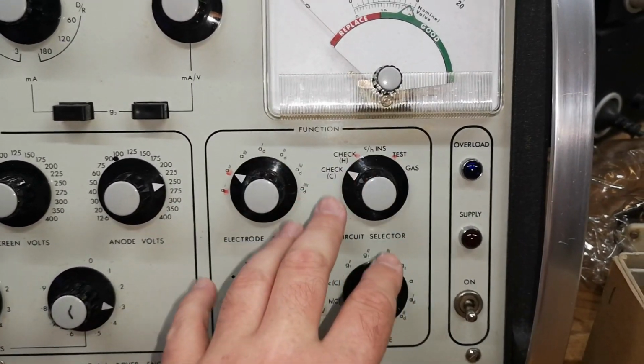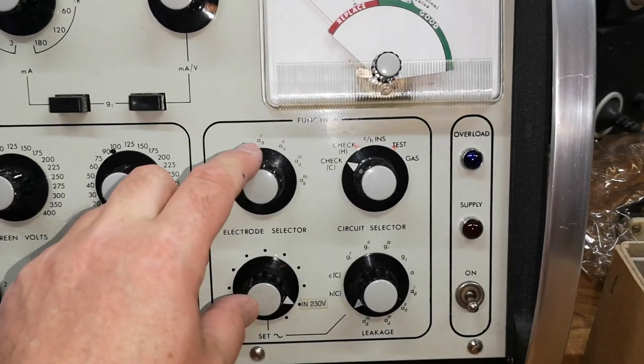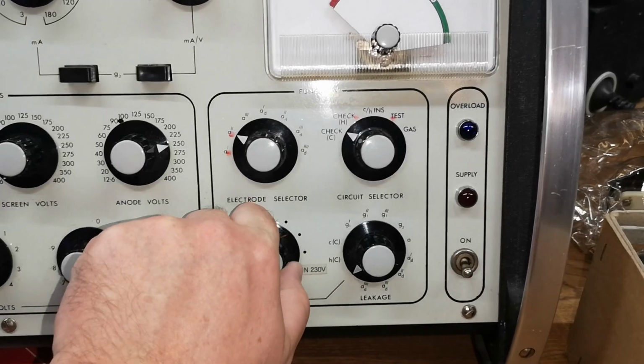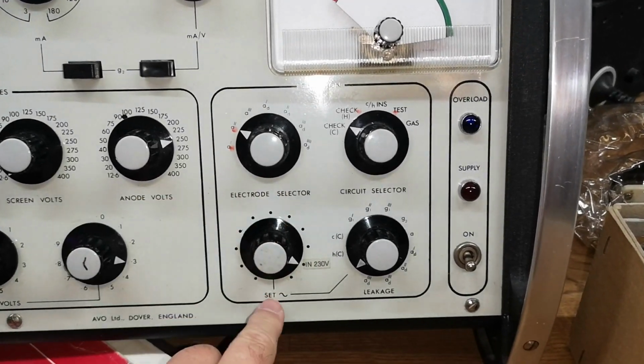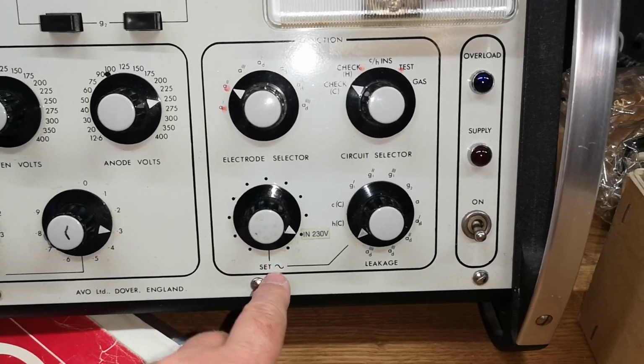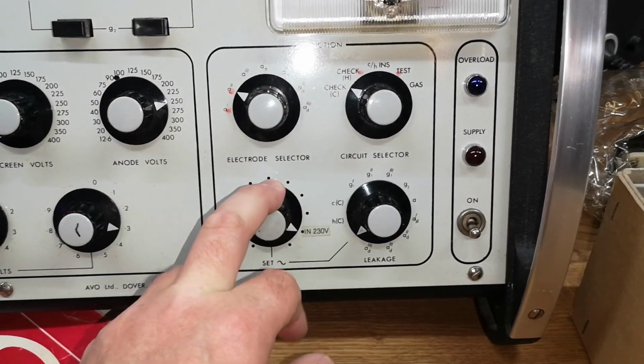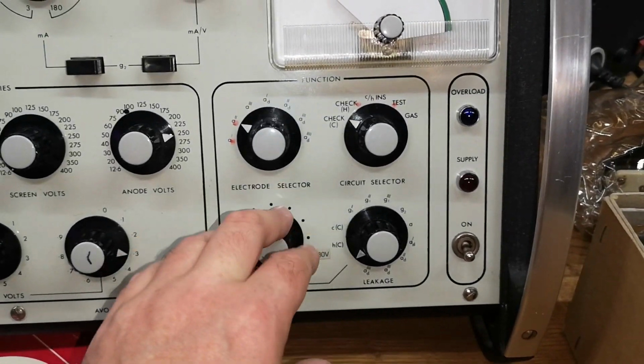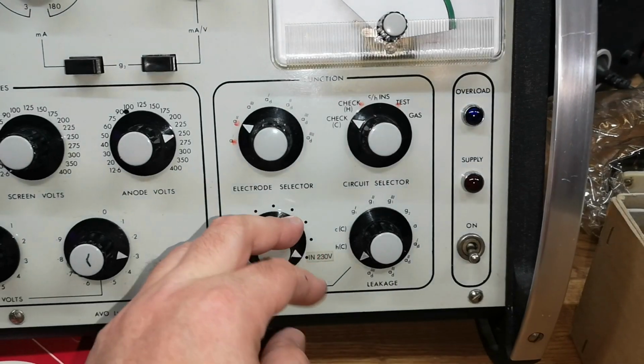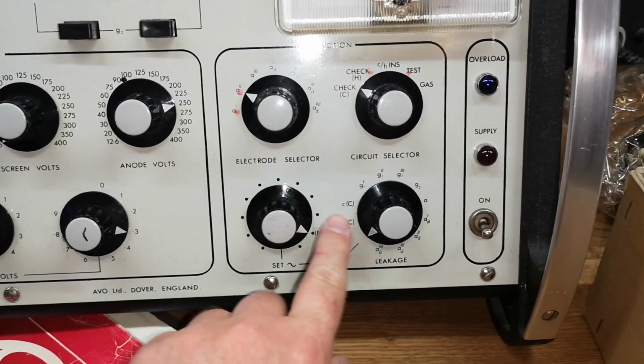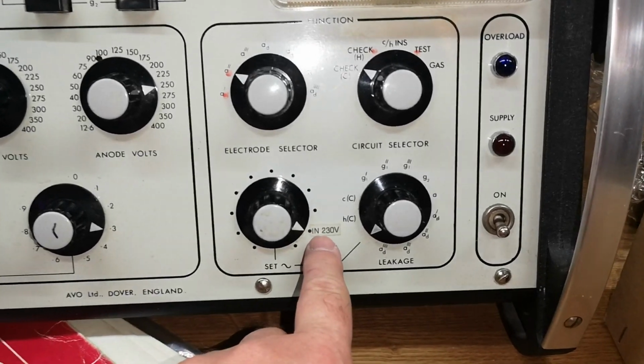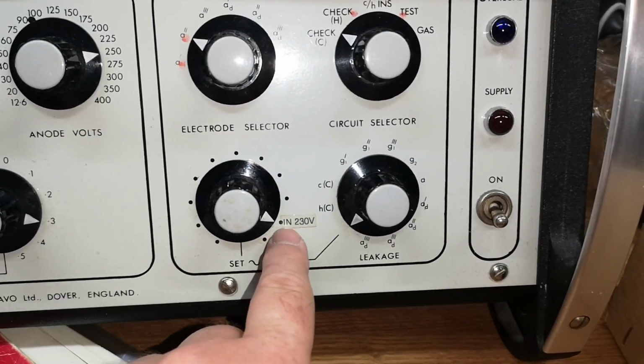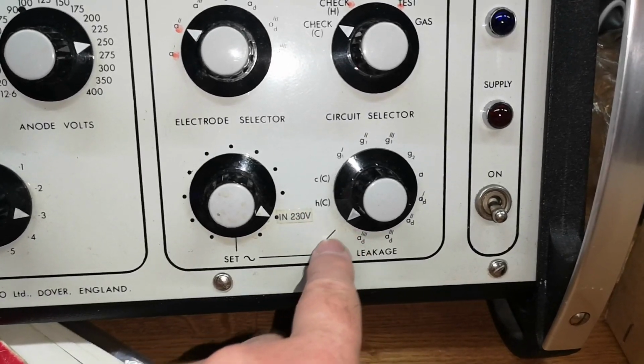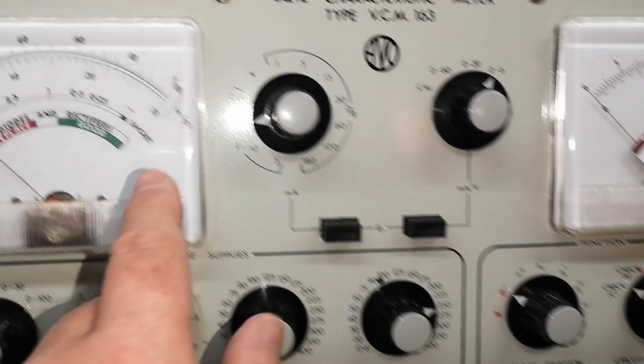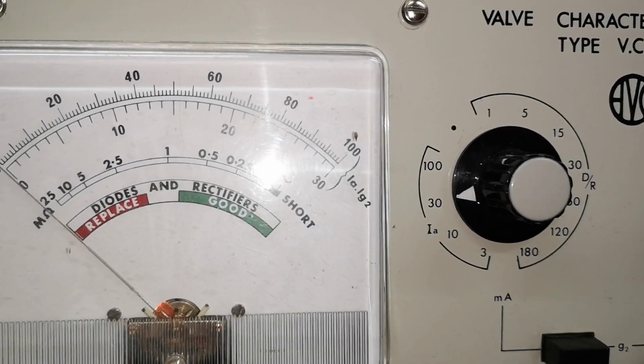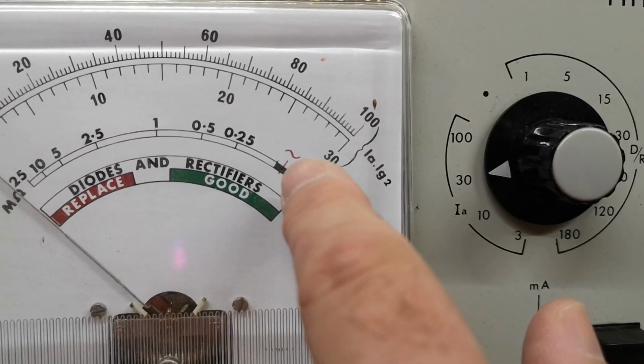So here is our measurement and function setup, and here we got the set, and this is for the AC mains. This is actually how you calibrate the unit, so that all the voltages and gains and stuff like that is going to be accurate. At the moment, it's actually done by just putting it right here and dialing in 230 perfectly correctly, and then just set the readout. Oh, maybe I should turn this off to that exact point.